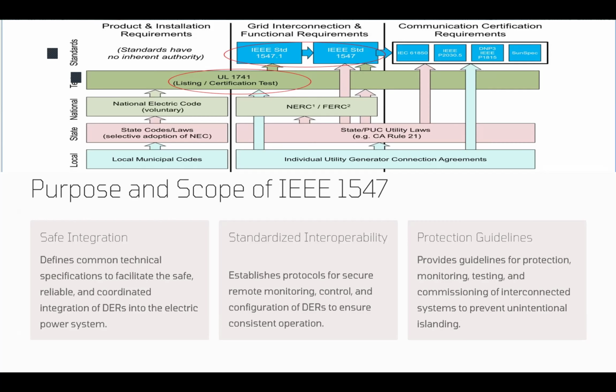Now, we have an aspect of interoperability within the purposes of this IEEE 1547, which basically makes sure that the DER are not just connected, they can also be coordinated with the grid. Okay, so it mandates some communication and control capabilities, so that utilities and utility owners can remotely monitor, control, or even adjust the DER parameters. It could be the power factor, active or reactive power, or those ride-through settings that we are going to discuss. Besides that, it enables the DERs to have an event-based dispatch capability. Okay, so a utility can ramp down the DER output during emergencies or schedule a certain setting for the peak demand.